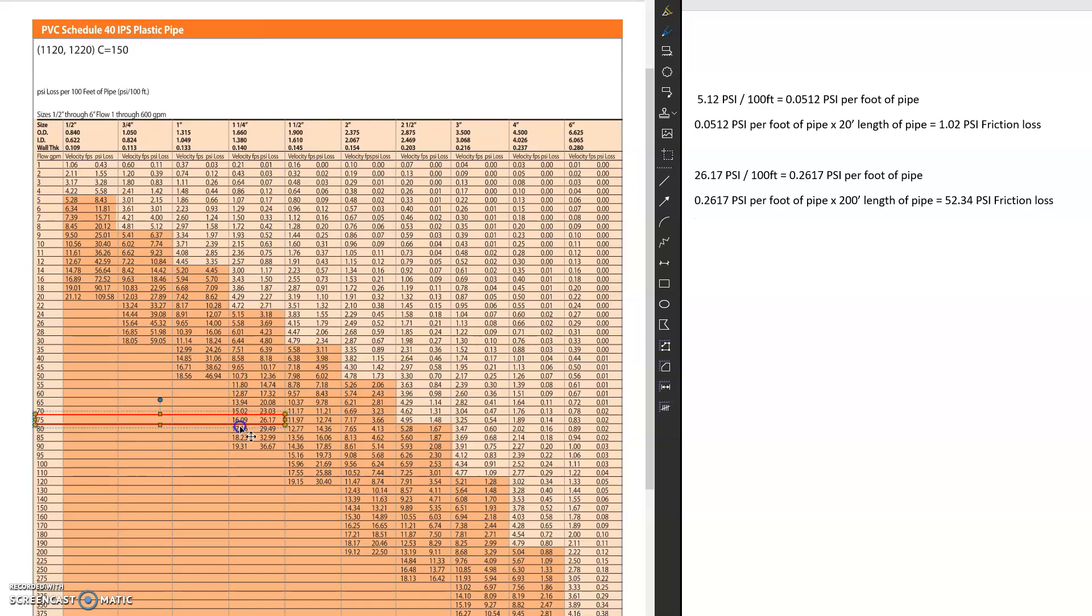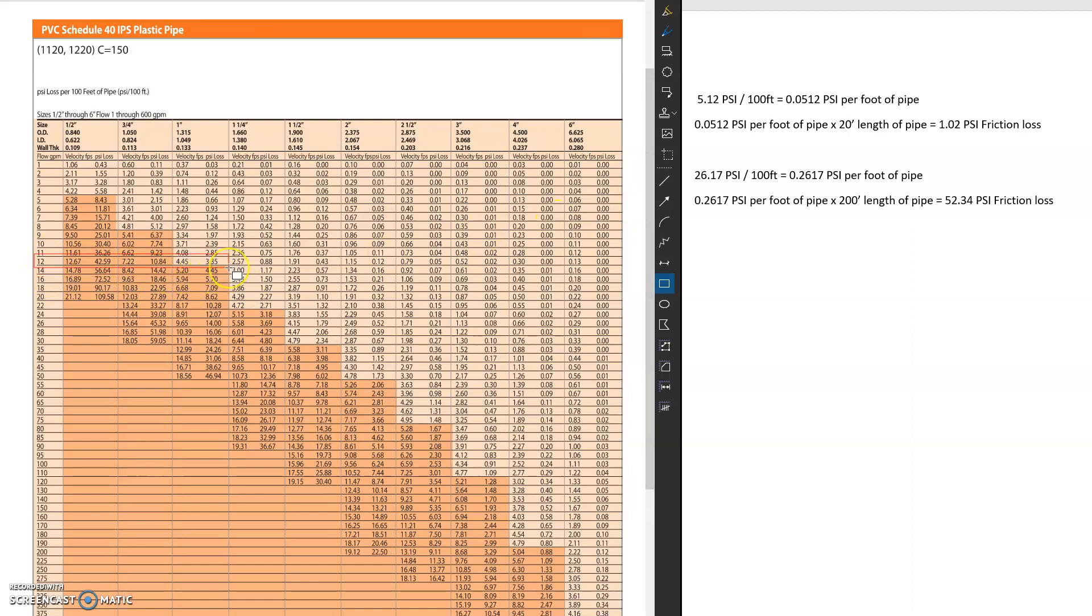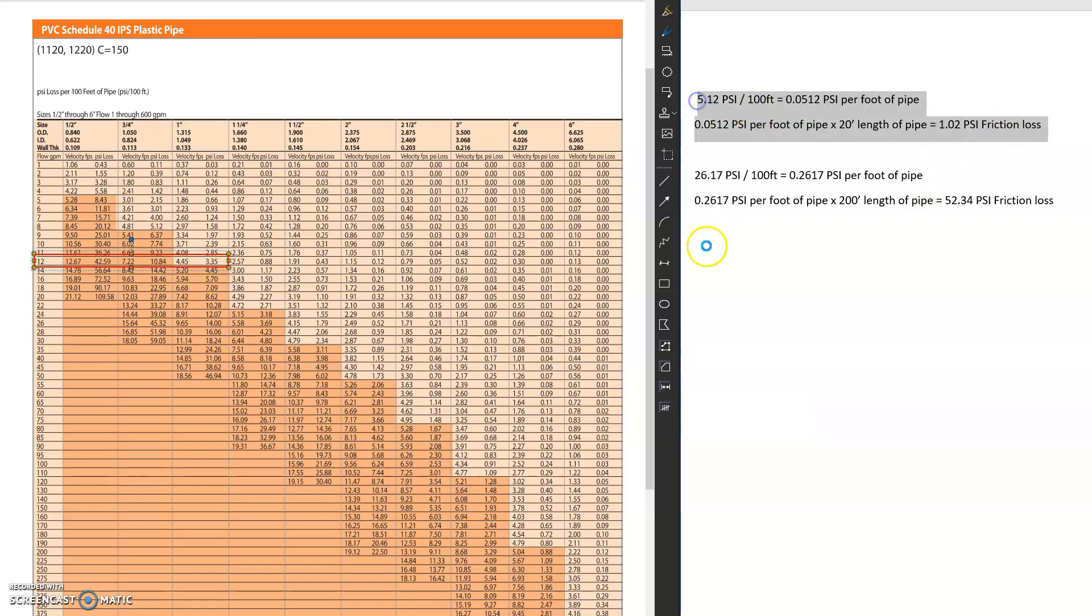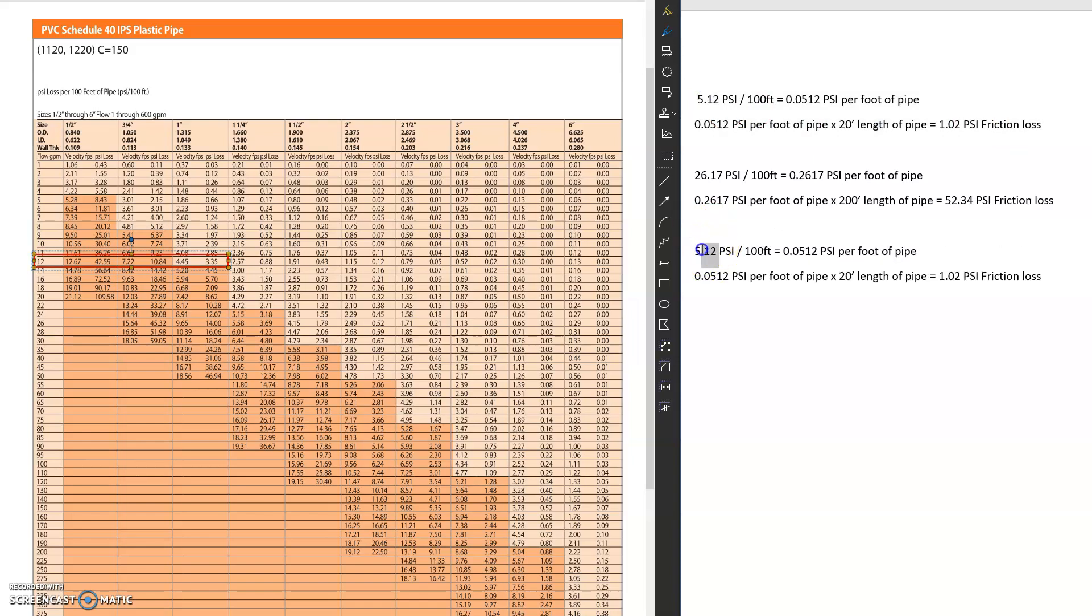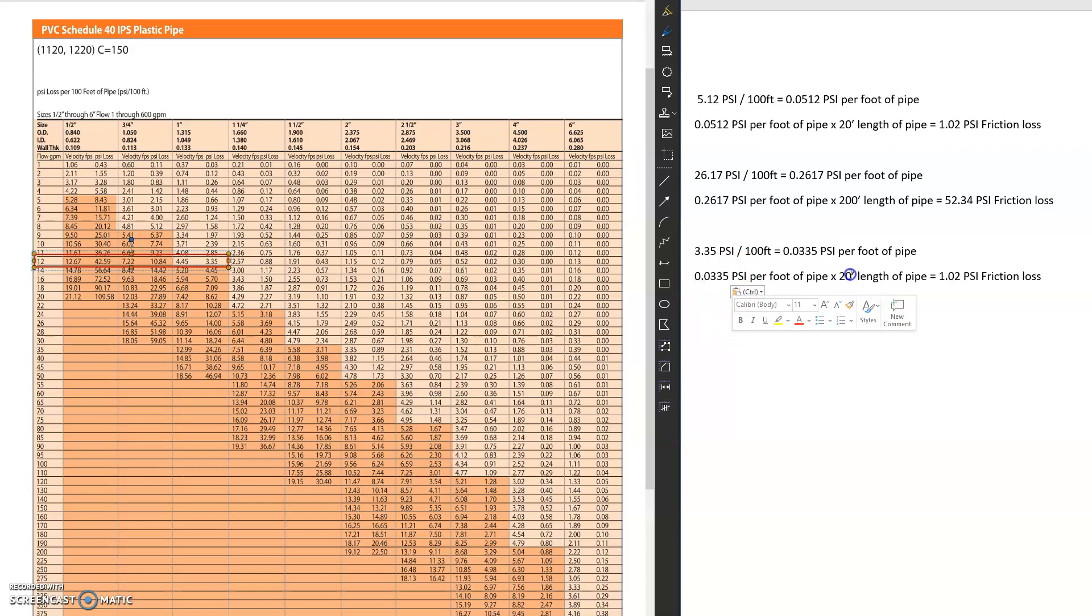So let's do one final one over here. So let's say I had 12 GPM. We're going to do this one at the one inch, so where the pipe is sized correctly. So that's 3.35. And that's going to be 3.35. I'm going to make this 30 feet this time for you guys. So 0.0335 times 30.